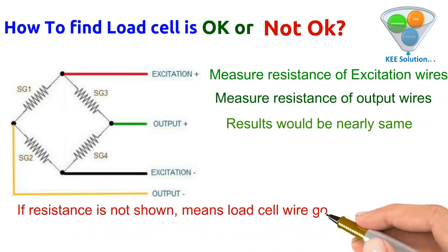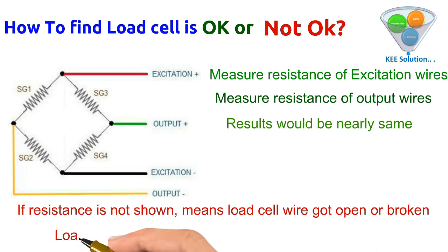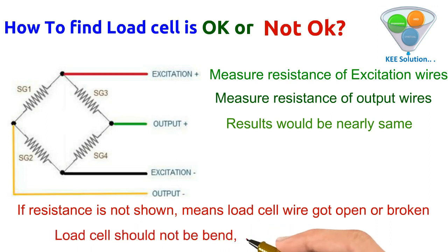If the resistance is not showing a reading, the load cell wire may be open or broken. A load cell should not be bent, twisted, or damaged. If a load cell has scratches, bends, or twists, it will affect its performance.